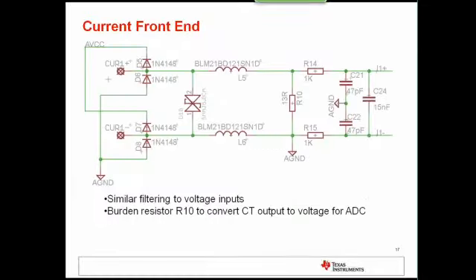This shows the current front end on our F6736 meter. You have clamping diodes on the end, and a two-way diode, D10, just in case the burden resistor fails. If the burden resistor fails, that would cause a large voltage on the measuring device, which can damage it. There's also anti-aliasing filter circuitry at the end.